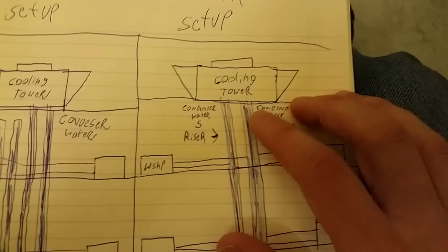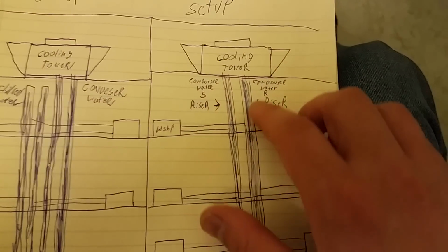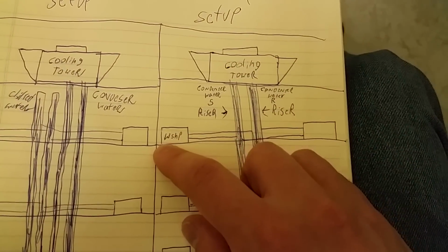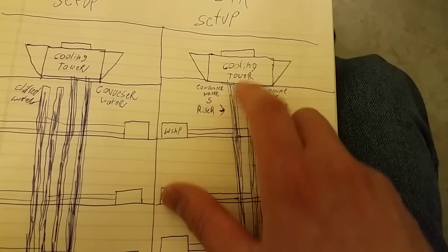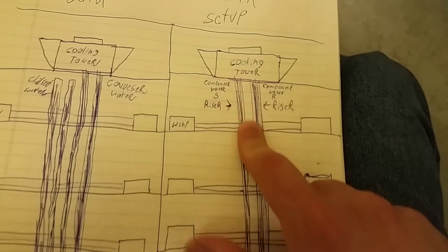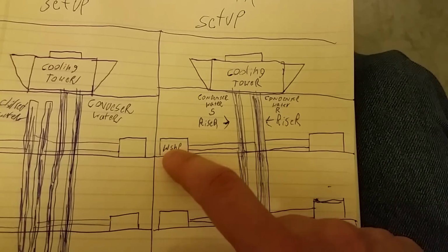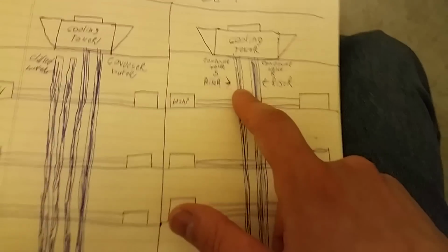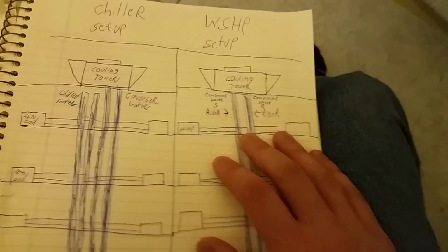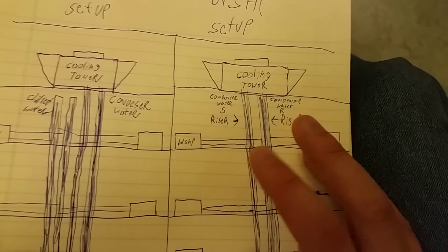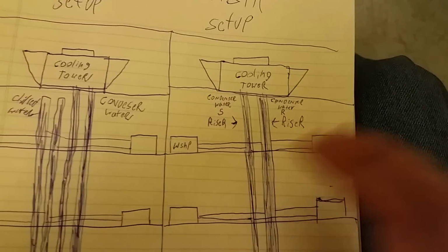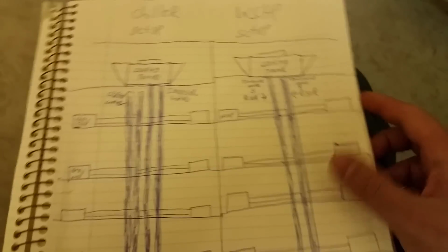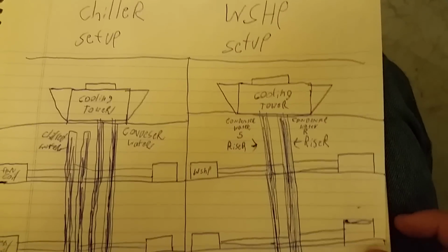Now, you want to make sure in the summer when it's 90 degrees out, your water temperature is below 80, because sometimes these will go off on high head pressure. If the water coming back from the tower is 85, 90 degrees, that's no good. These things are going to be running mad hot. We had that problem over my dad's building, but that was a closed loop system. I'm not going to get into that in this video, but we had to spray water on the bottom of the coil because it just couldn't cut it. If there's anything I'm missing, I would love someone to tell me. I'm pretty sure M&HVAC will be watching this.